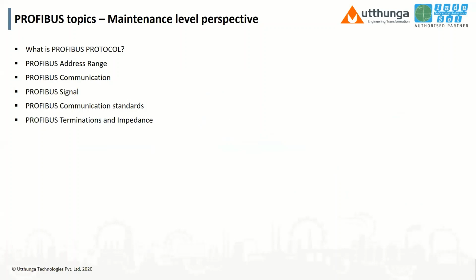So as part of today's discussion, what we'll be looking into is Profibus technology from a maintenance perspective. I will be touching on what the Profibus protocol is and the addressing mechanism that is used in Profibus technology, how Profibus communication works, and some of the signal aspects that we need to look into in Profibus, and the communication standards and physical requirements of maintaining terminations in Profibus line segments, and impedance values that are required to be maintained in Profibus.